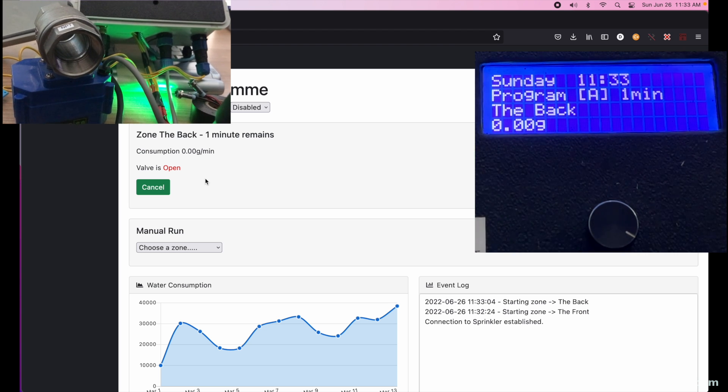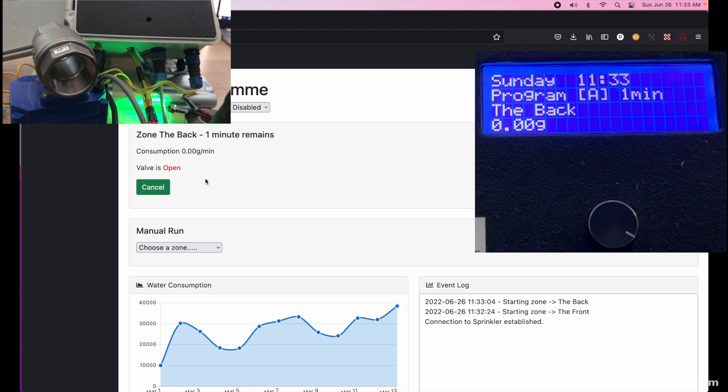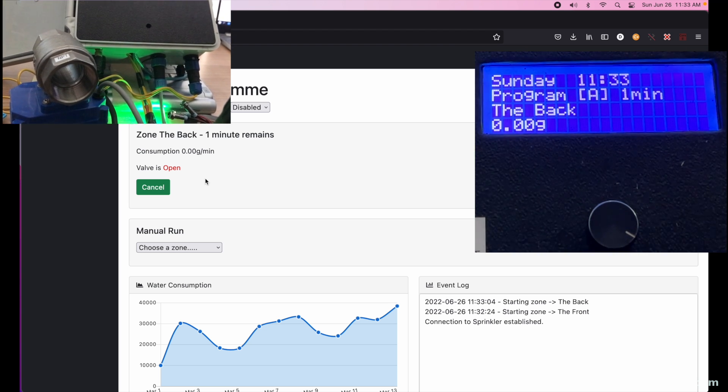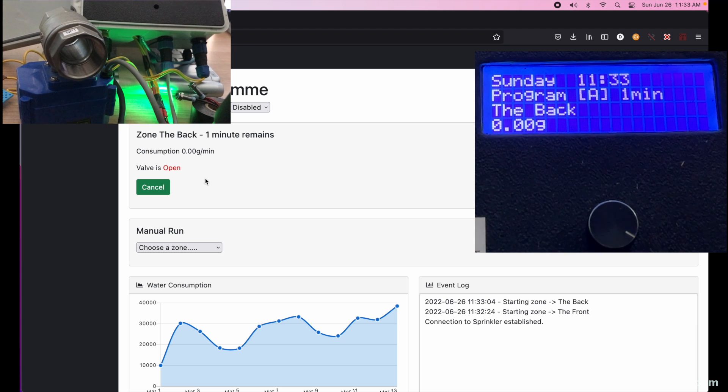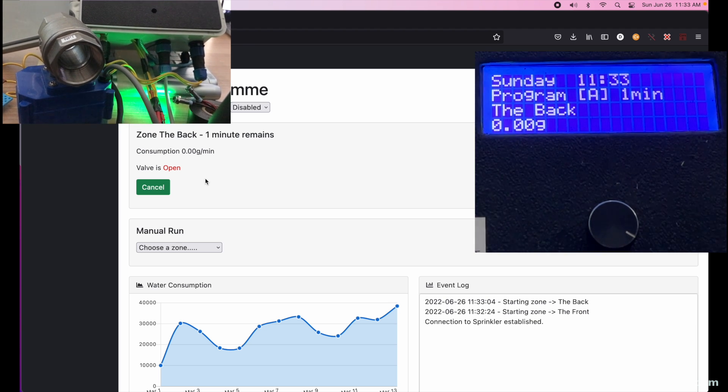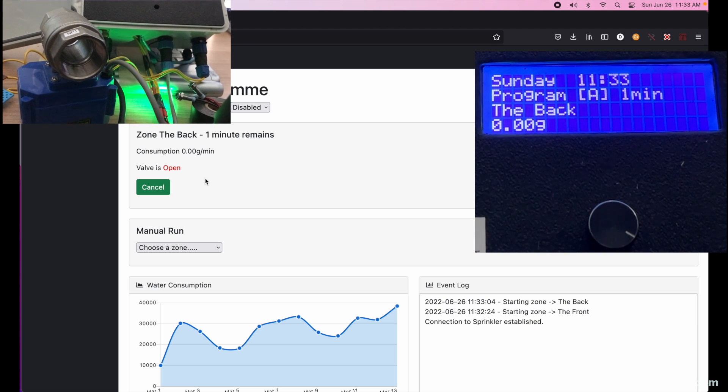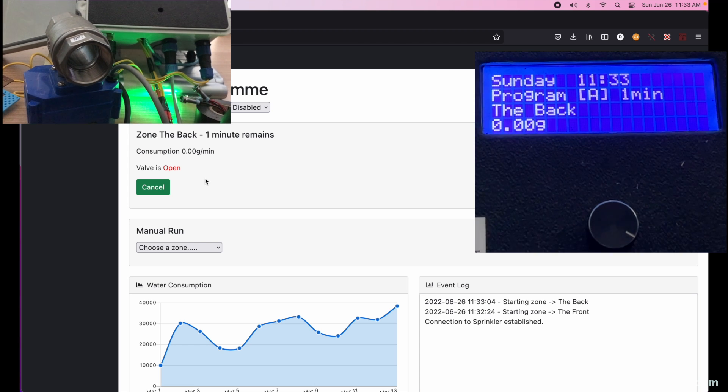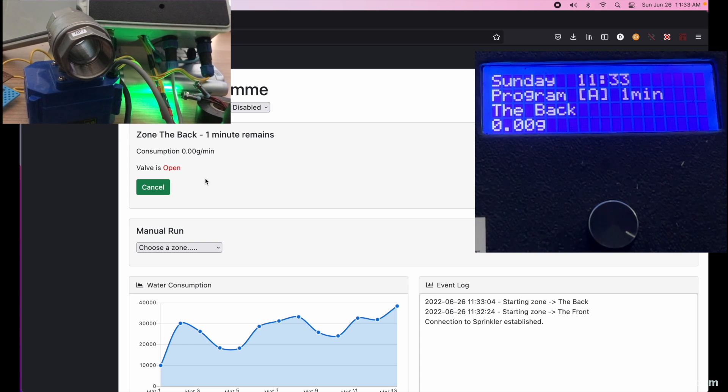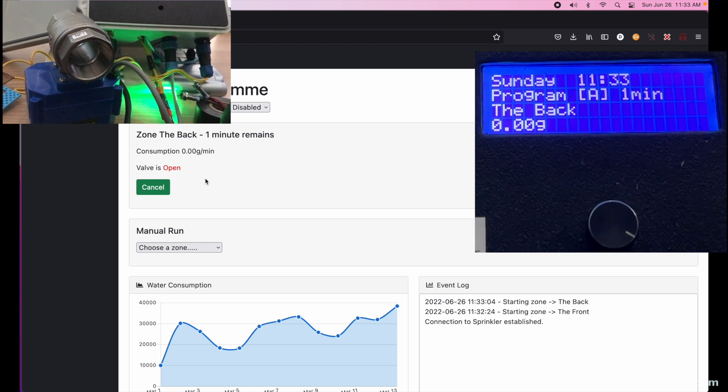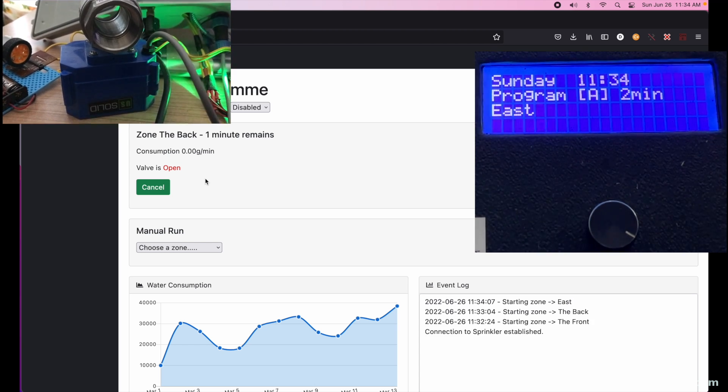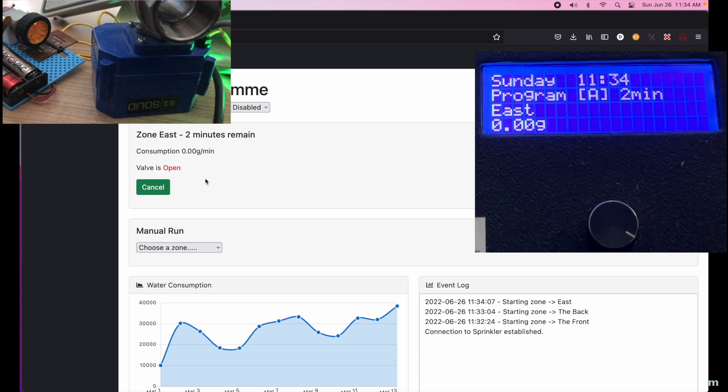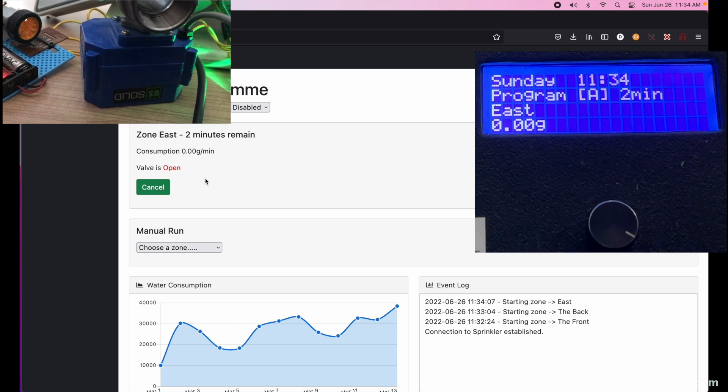It just moved over to the second zone Back, also one minute zone. We heard the relay click, saw the log update. Obviously the valve stayed open, there was no reason to close between zones and the consumption went back to zero. I'll skip ahead to the third, and this one I'm going to manually cancel from the front panel.